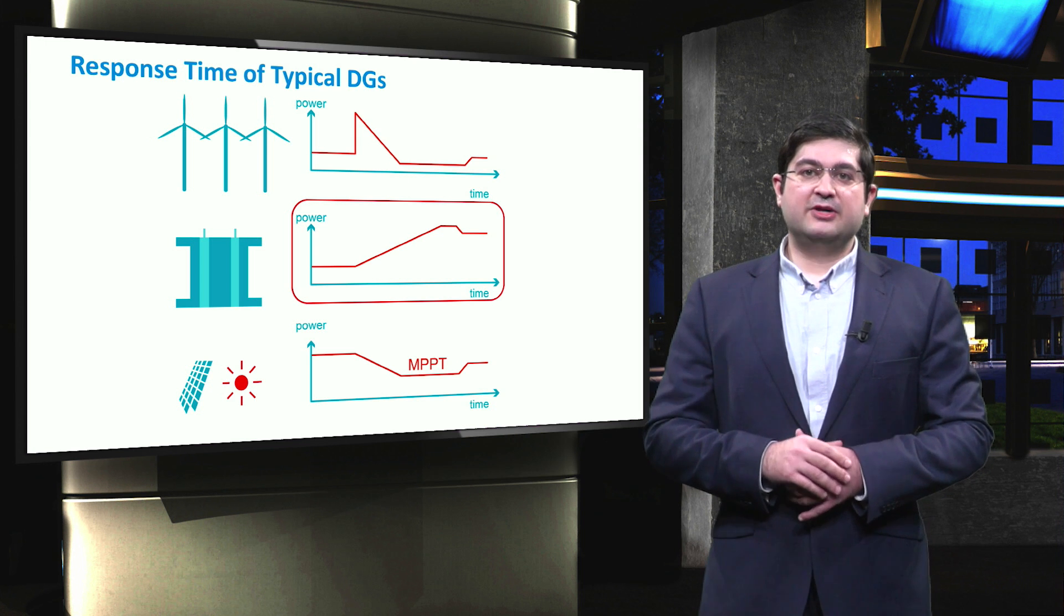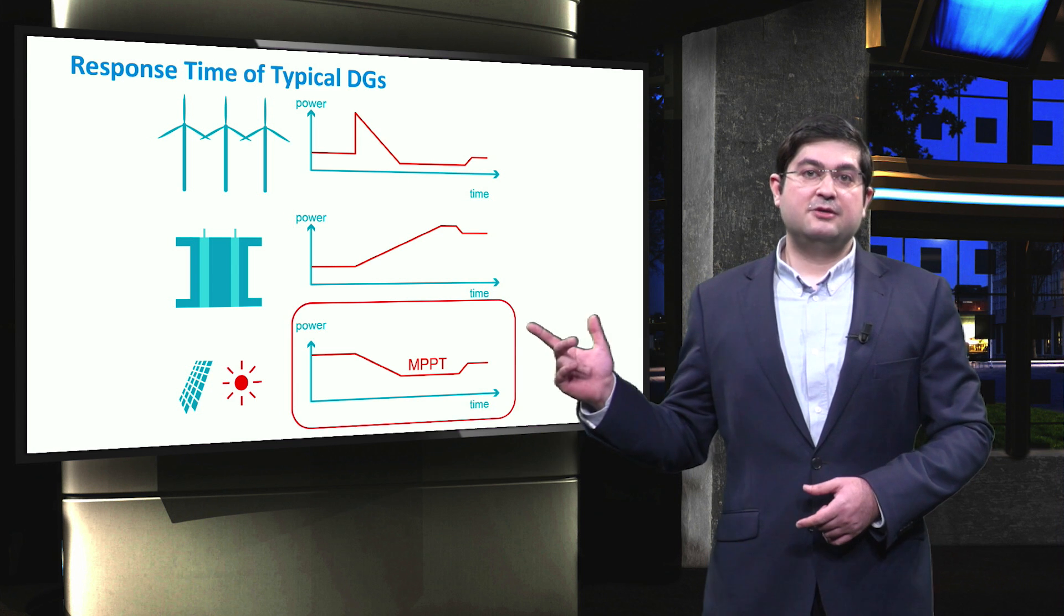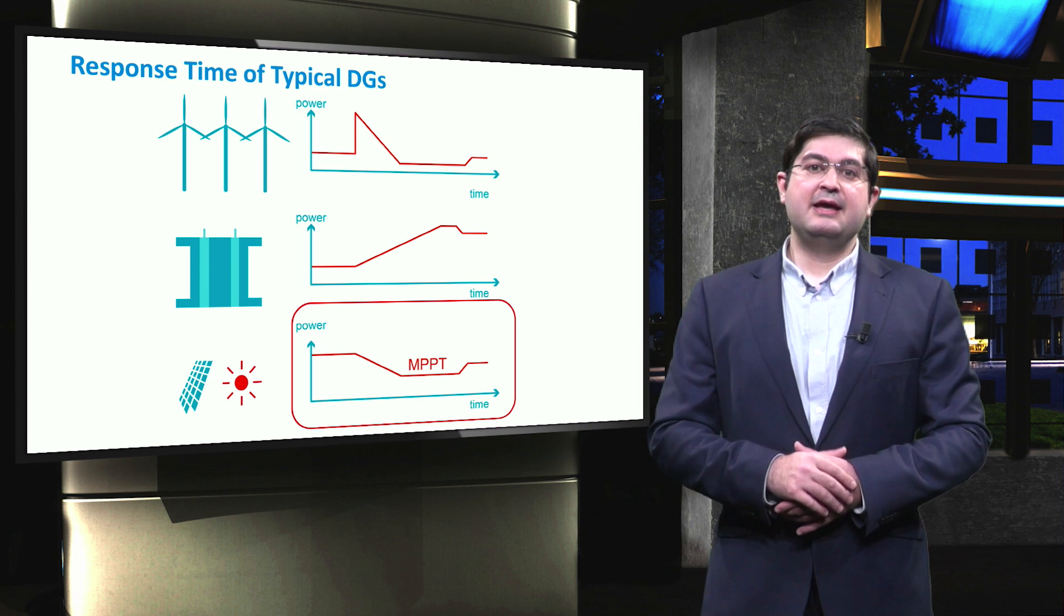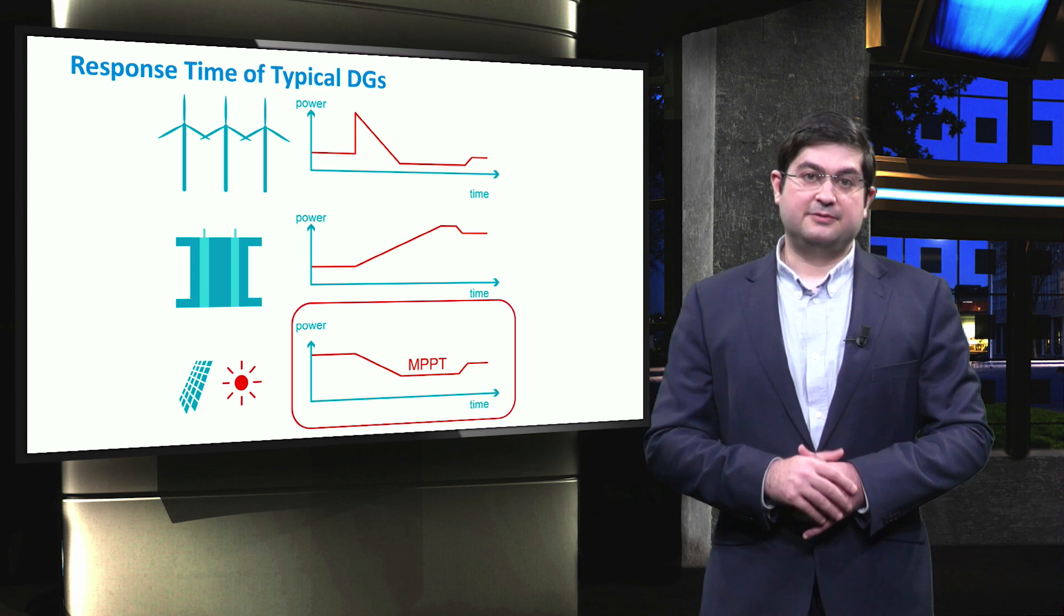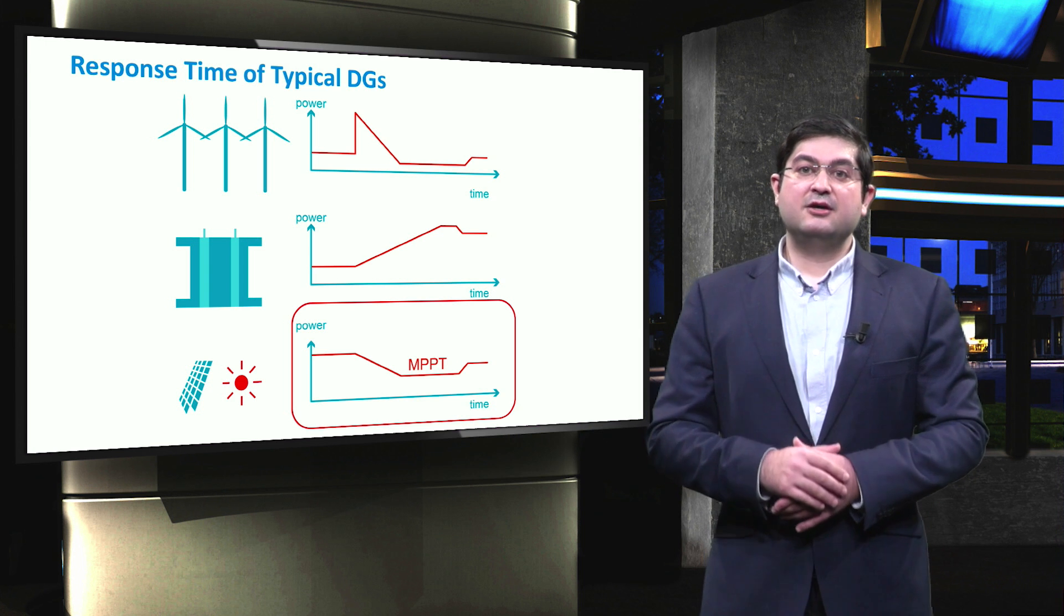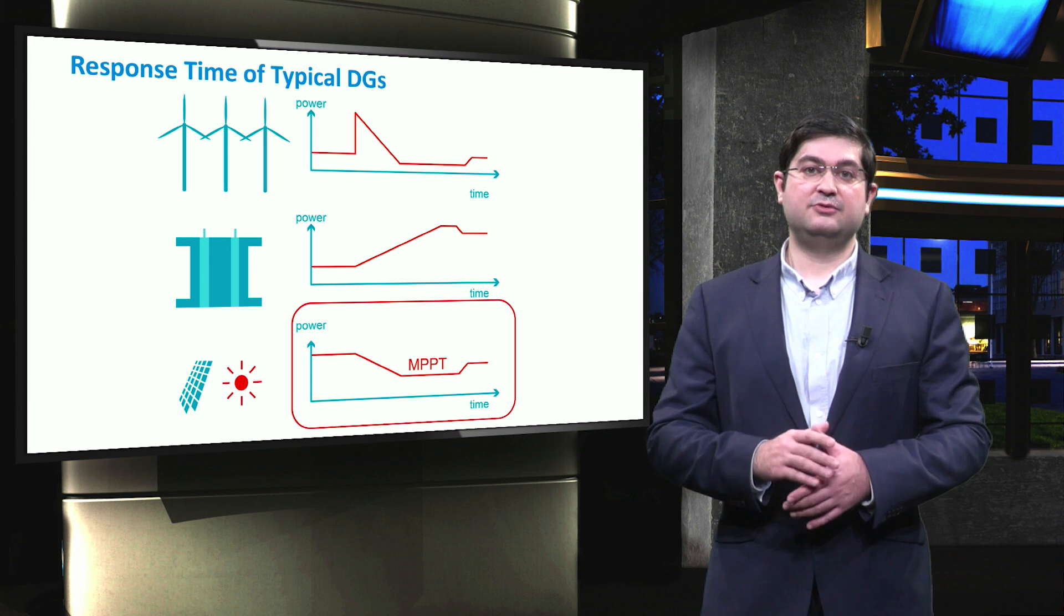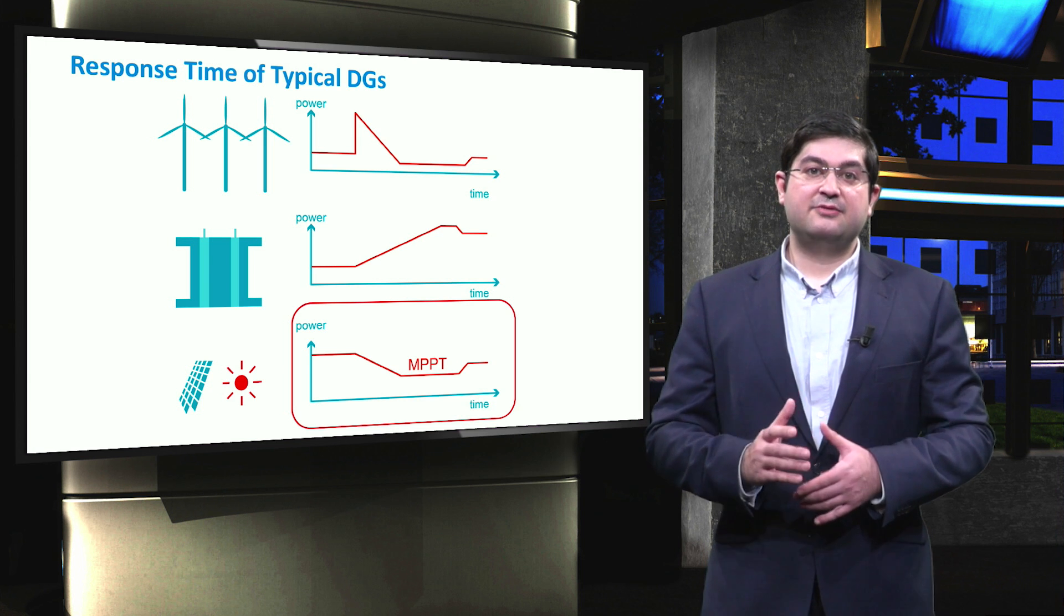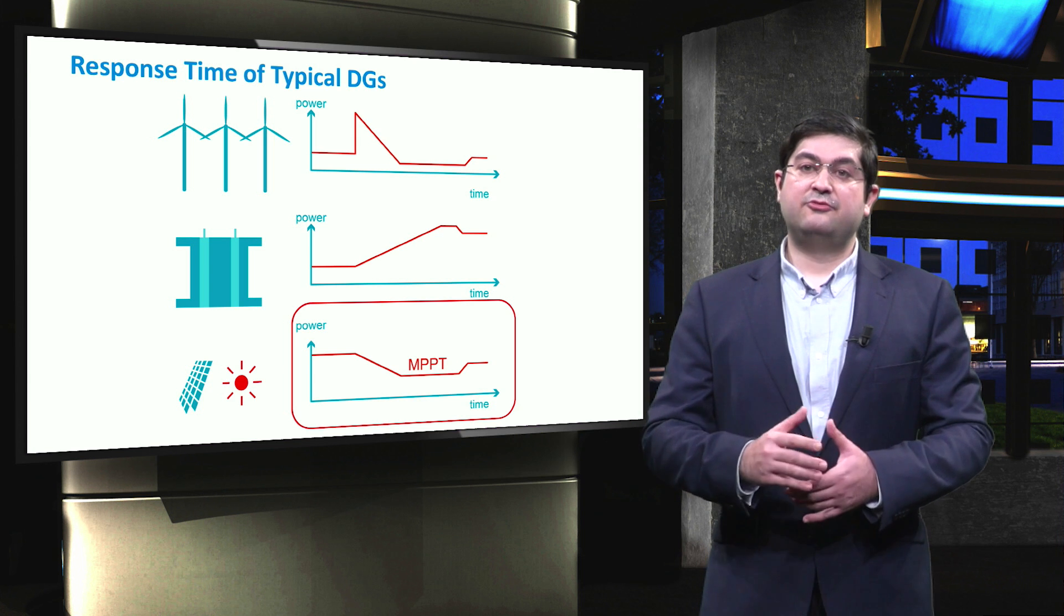Then, what about PV solar units? In fact, they are typically operated at their maximum power point, at which obviously they are not able to increase their active power. Therefore, photovoltaic solar units cannot be used to fully support the frequency, particularly during the moments where an increase in power generation by PV solar units is needed for frequency control.